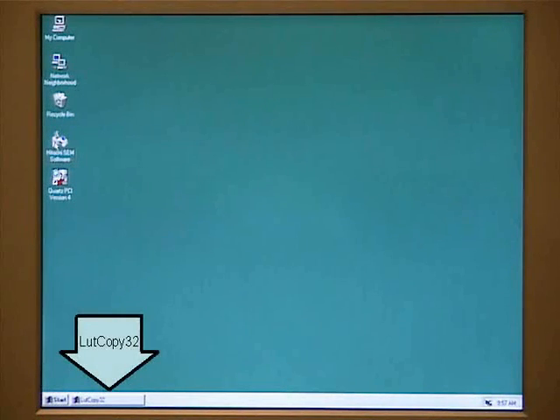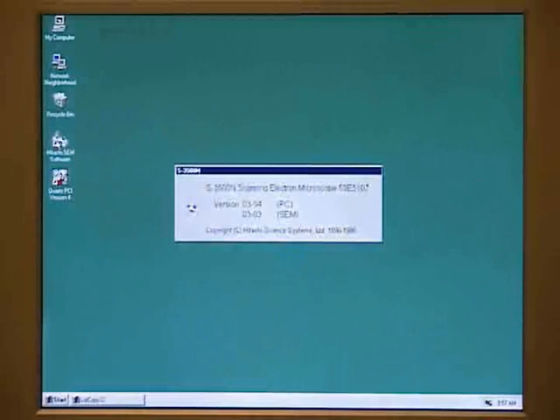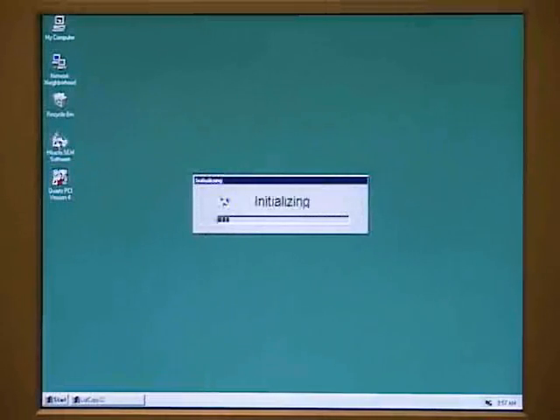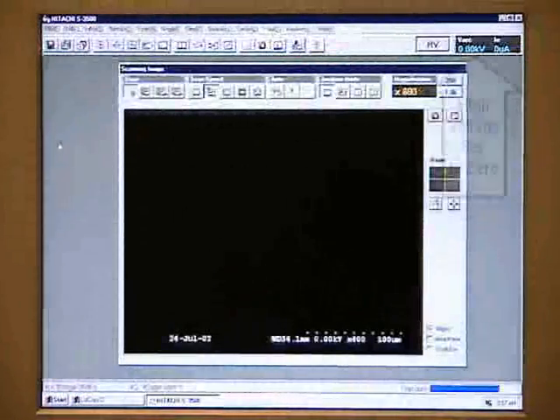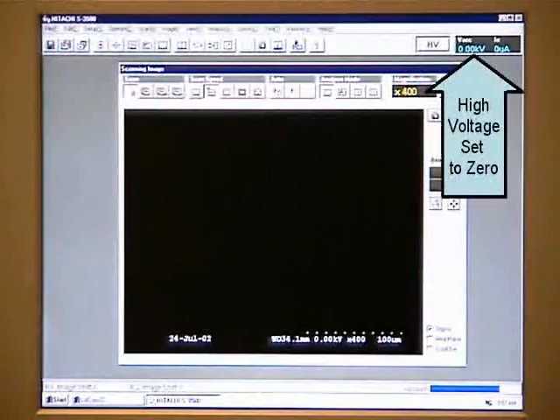Before we begin using the SEM, we must make sure that the LUT Copy 32 software is running. If it is not running, we must open the application. We can find it by going to Start, Programs, and then Startup. Start the SEM software by clicking the icon on the desktop. Once it is loaded, we must make sure that the high voltage is off. Do not leave the high voltage on when venting the chamber.